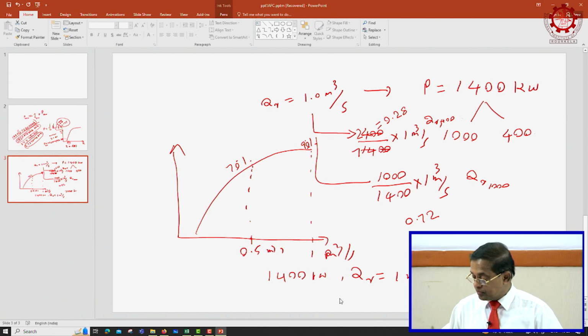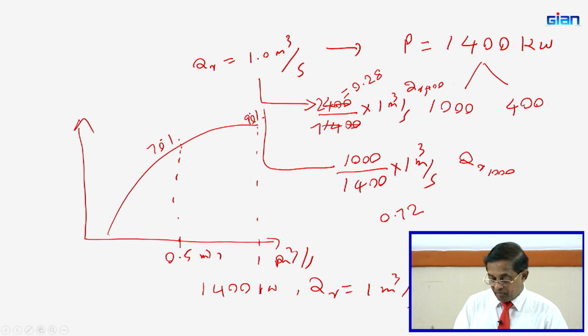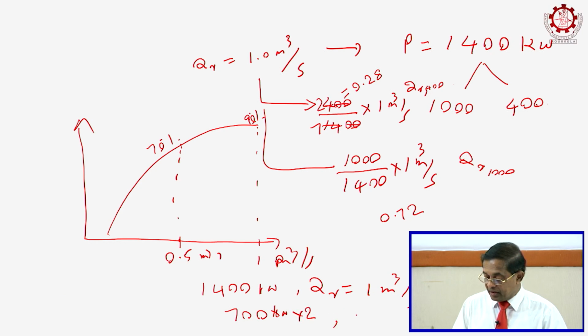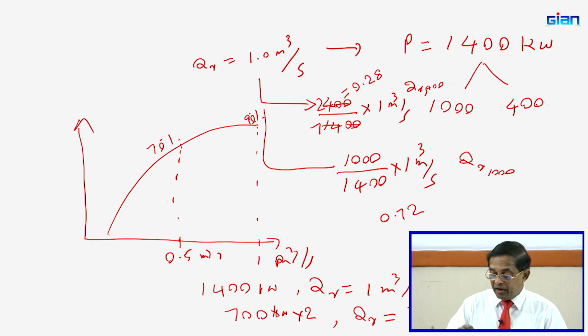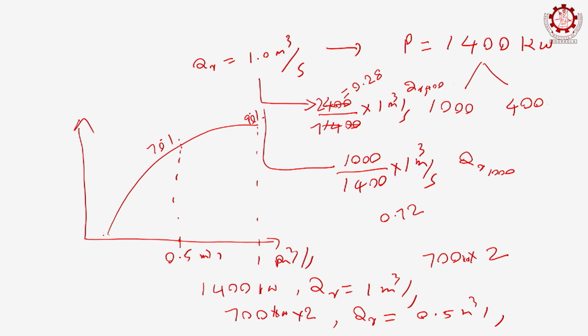700 kilowatt into 2 machines, where Q rated per machine is 0.5 cubic meters per second, right. Now, your machine has the maximum efficiency at 0.5. Your 700 kilowatt machine will have an efficiency curve something like this. At 0.5 it will have 90%, and you can see that your machine will mostly operate at this point if you have the smaller machine.